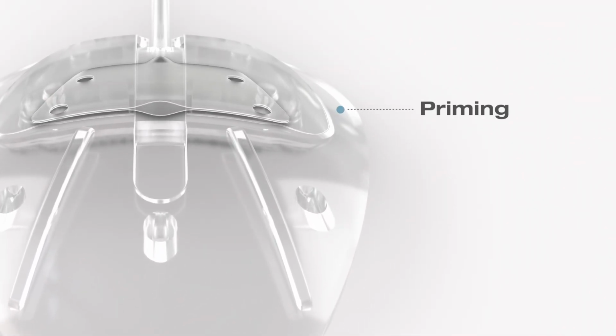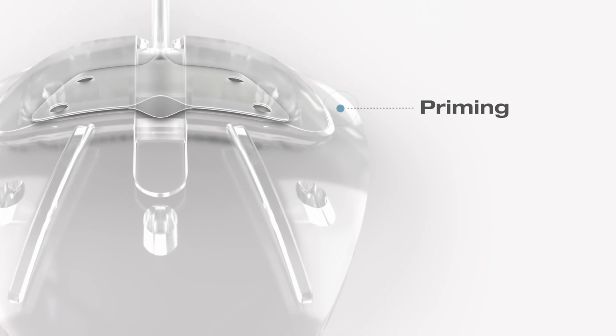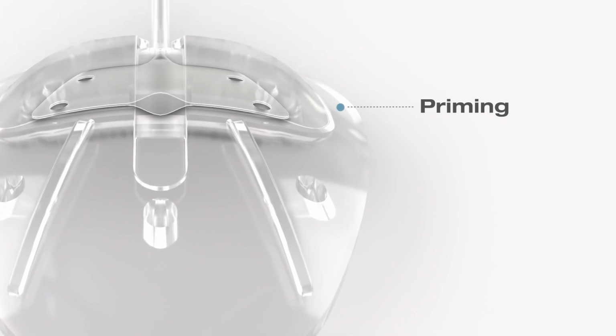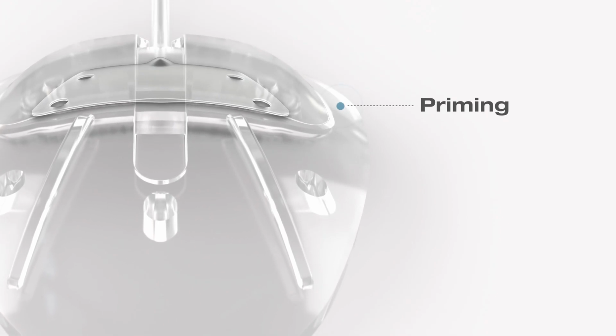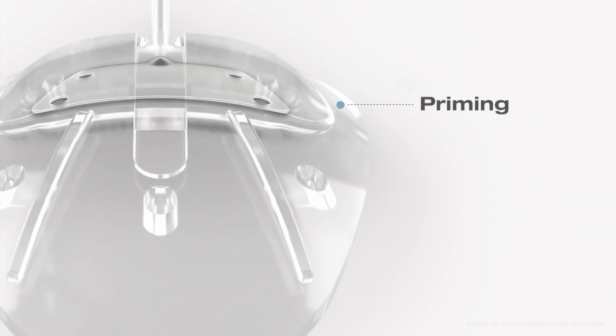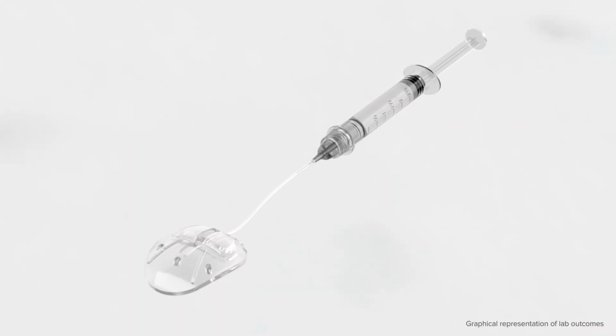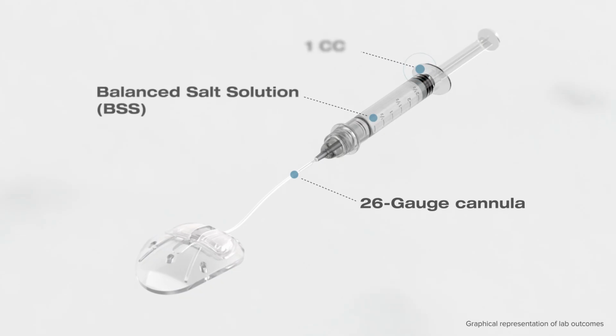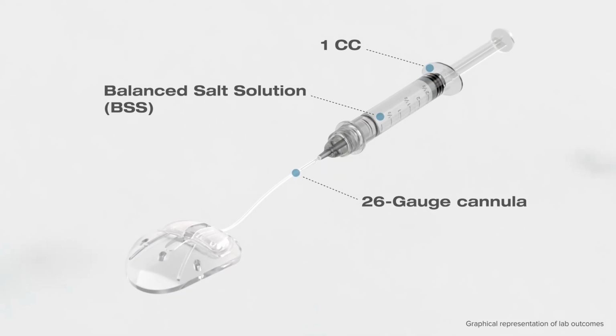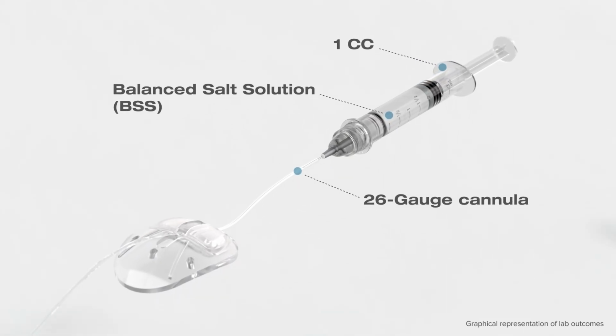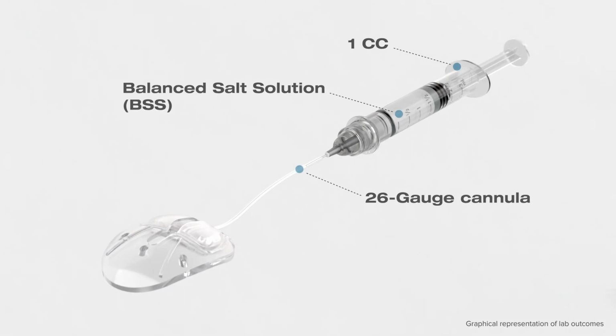To get started with the Ahmed glaucoma valve, the device must be primed. Priming removes air from the device, separates any binding of the valve sheets that may have temporarily fused together during the sterilization process, and allows for optimal functioning once implanted. Priming the device is achieved by injecting approximately 1 cc of balanced salt solution into the distal end of the drainage tube, using a 3 cc syringe.